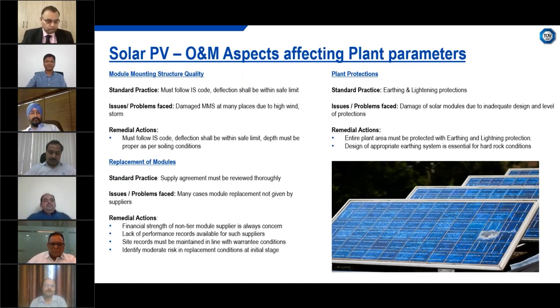Module mounting structure quality, MMS quality - standard practice must follow the IS code for deflection and other parameters. The issue we've seen is MMS being damaged in many places due to high wind, storms, or heavy rains. The remedial action developers should consider is to follow the IS code, keeping deflection within safe limits and proper depth conditions. Also, replacement of modules damaged over time - in many cases module replacement isn't given by suppliers, so that needs to be considered. Plant protections, standard earthing and lightning protection, should be in place to avoid damage to solar modules from inadequate design and protection levels.